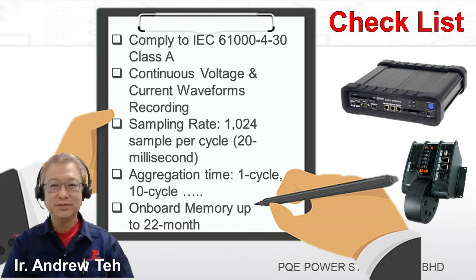Feature 4: the power quality analyzer must come with both single-cycle and 10-cycle aggregation time throughout the recording period up to 22 months. Single-cycle aggregation time is needed for accurate and detailed voltage dip analysis, enabling correct voltage dip mitigation recommendations. Feature 5: it must be equipped with on-board memory able to store all three-phase waveforms and all electrical parameters at 1024 samples per cycle for up to 22 months. Feature 6: it must come with a valid accuracy validation certificate traceable to a valid SIRIM calibration certificate.